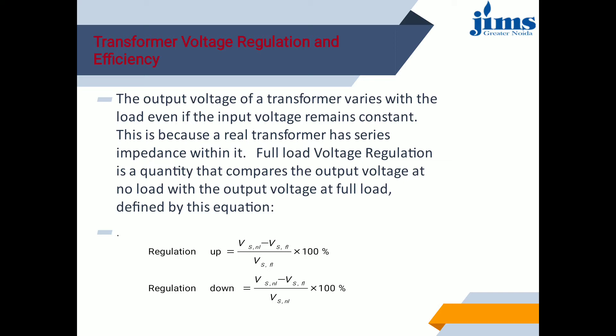The figure of merit which determines the voltage characteristic of a transformer is termed as voltage regulation. It is usually expressed as a percentage of the rated terminal voltage. It is defined as the change in magnitude of terminal voltage when full load of a specified power factor is supplied at rated voltage, then thrown off to no load, with primary voltage and frequency held constant, expressed as a percentage. Voltage regulation = (Vs,nl − Vs,fl) / Vs,fl × 100, or alternatively (Vs,nl − Vs,fl) / Vs,nl × 100.